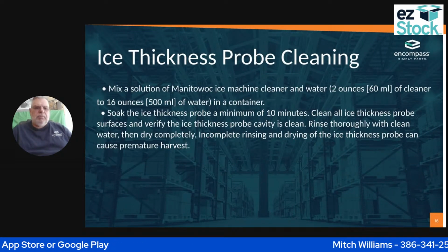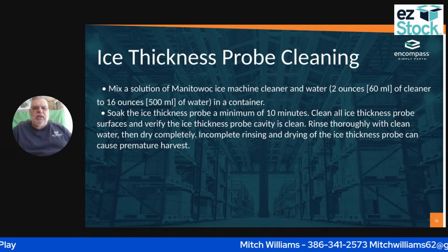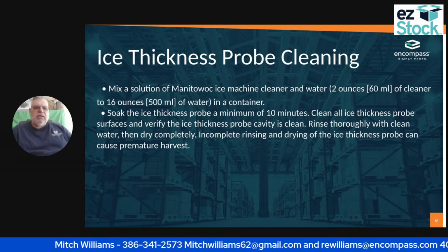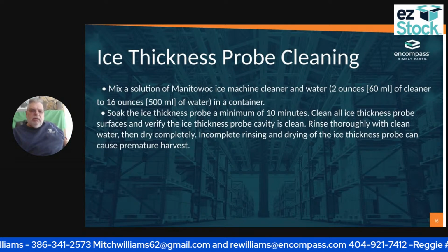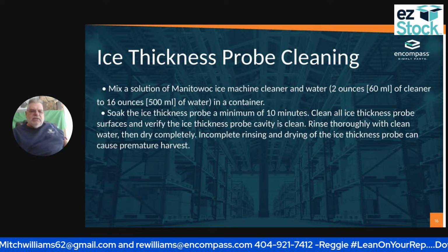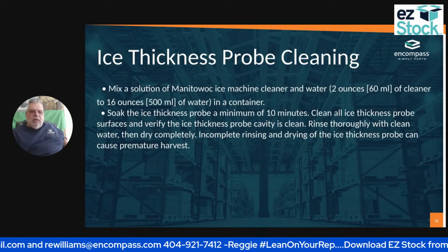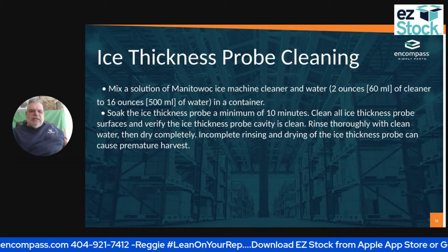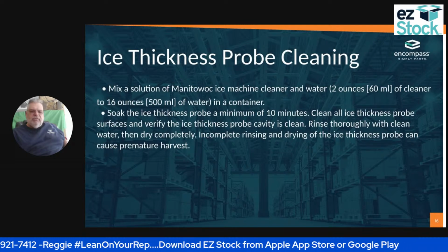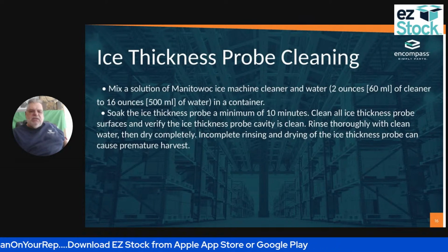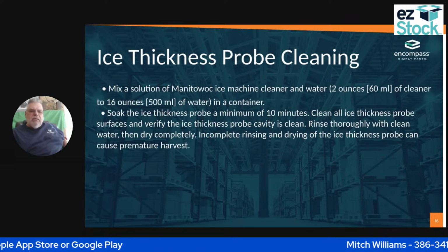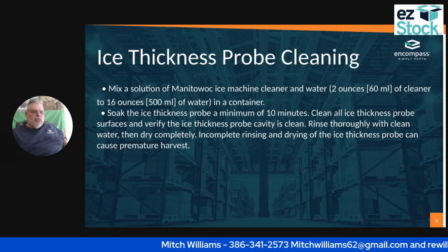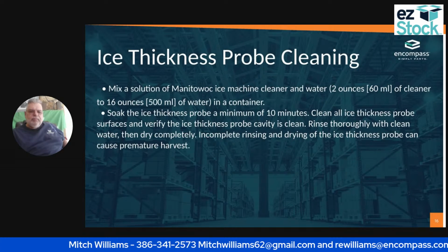I'm going to mix a solution of the Manitowoc ice machine cleaner and water, about 2 ounces of the cleaner to 16 ounces of water in the container. Soak the ice thickness probe a minimum of 10 minutes, clean the probe surfaces, and verify the ice thickness cavity is clean. Rinse it thoroughly with clean water, then dry completely. This is the only thing you're going to dry, your ice thickness probe.